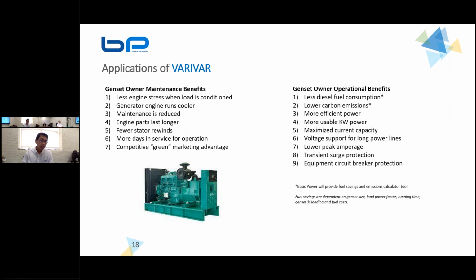And if you're the owner of this genset, there are a lot of benefits, like we mentioned before, like less engine stress when load is conditioned. And you also run into fewer issues like stator rewinds, because you're constantly having to maintain your generator due to heating. Like we mentioned before, the generator itself also has a rotor and stator, like a regular motor. So if you have heating in your system, the insulation will wear away, and the same exact issues we mentioned before in the harmonic slides will apply to your generator as well.